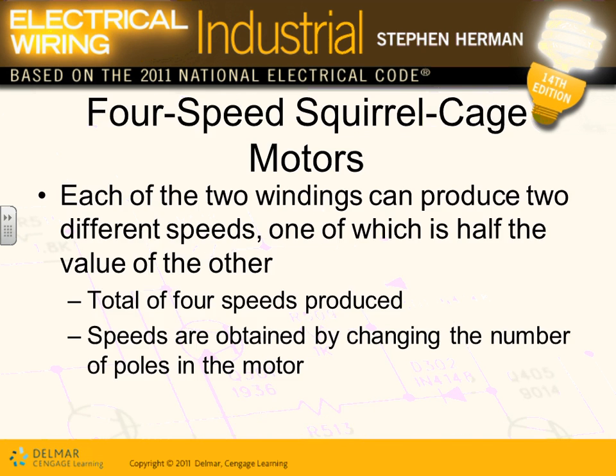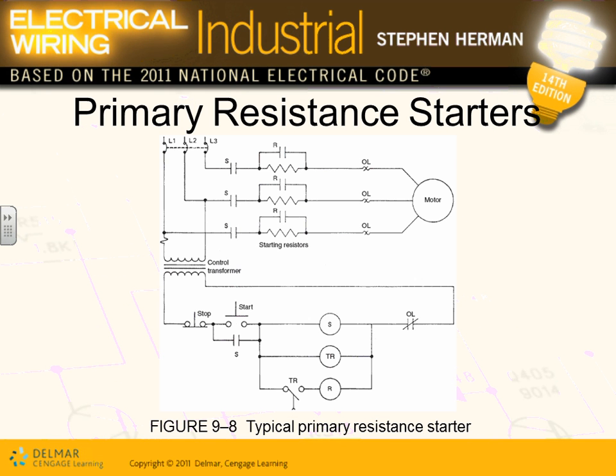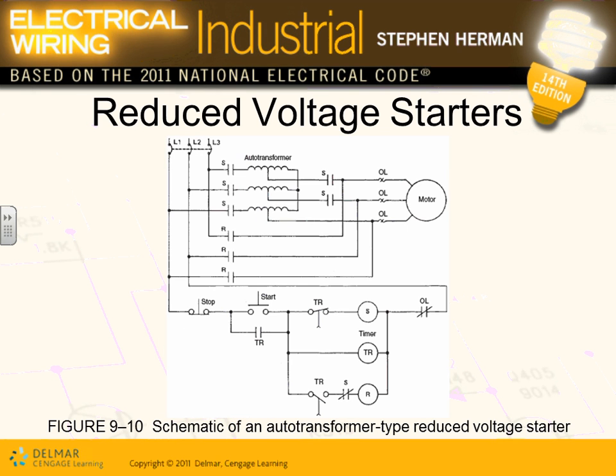What you're looking at right here is voltage reduction start. You reduce the voltage with a resistor, here, guys, or with the auto transformer. So you bring 480 here, you transform it down to 240. The motor starts slowly, gently, and comes up to speed within 10 seconds. Bam! You shunt the auto transformer out of the picture, which means you close the contacts across it, and your motor is running at full speed.